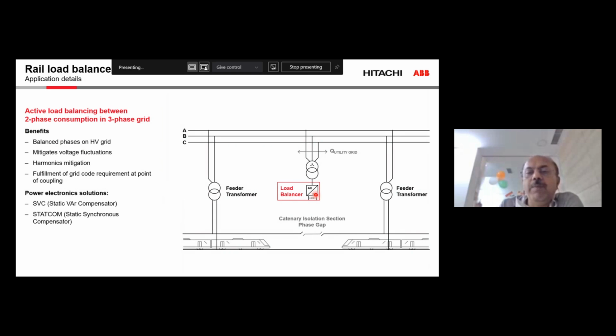If we look at what we call the load balancer, this is similar to a STATCOM, but it is not just connecting to the network to compensate for the reactive power, it will also compensate for the unbalance in the real power. When we have two phases connected and the third phase unconnected, this load balancer will draw the power from the unconnected phase and feed it to the other two phases where it is connected, and to the extent of unbalance it will correct it, so that the network will not feel any unbalanced currents flowing through as part of the real power feeding into the catenary.